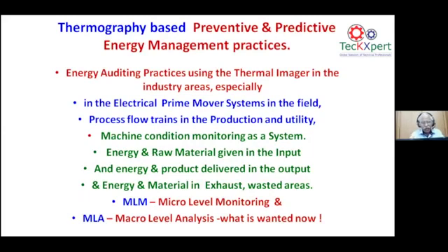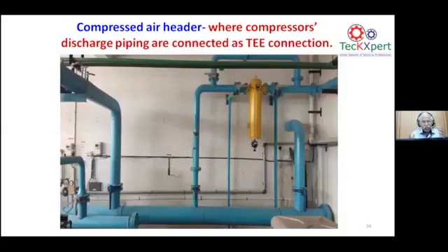The macro level analysis will definitely pave a way for how the utility equipments are operated within their healthy ranges. You can see it is not only on the process pipings and the water, but on the air also. Piping plays a major role to see to it that when the compressor has generated 1000 CFM, it has to be transported to the process smoothly. You cannot have any T junctions in your compressor house. Any T junction is a point of turbulence, it's a loss to us. Let us see the thermal image of this.